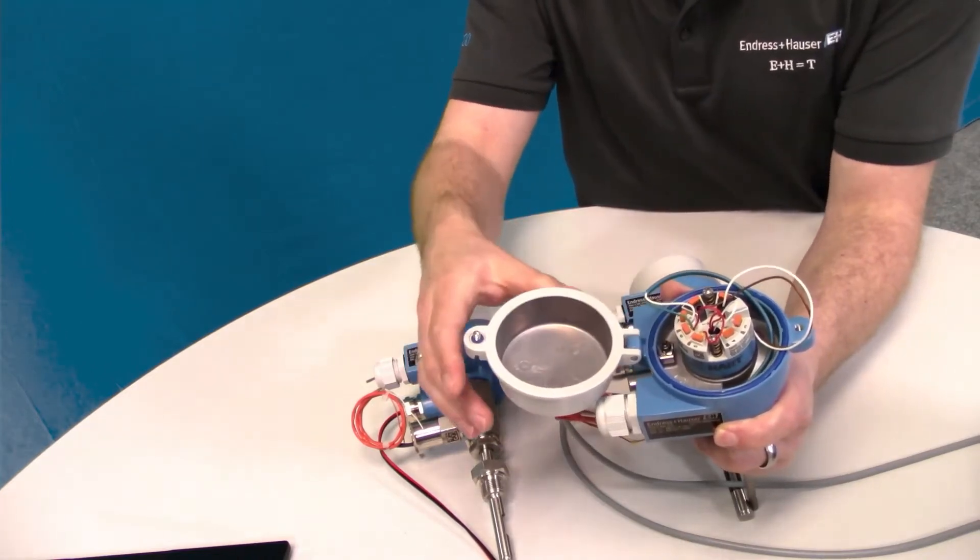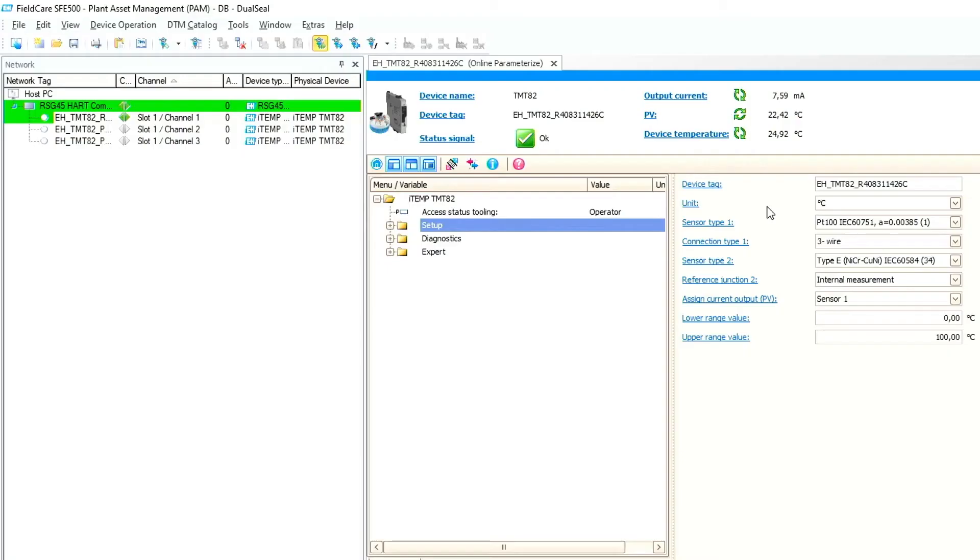Let's have a look into the configuration of this. Here you see the setup of our TMT82 in FieldCare. Key settings are here. Sensor one is configured as an RTD PT100 like ordered for the sensor measurement. And sensor type two is configured to type E thermocouple. Output is assigned to sensor one only because the measured temperature should be output.